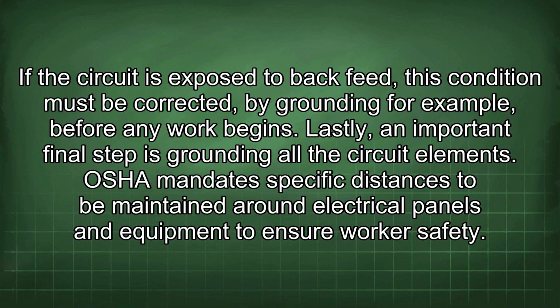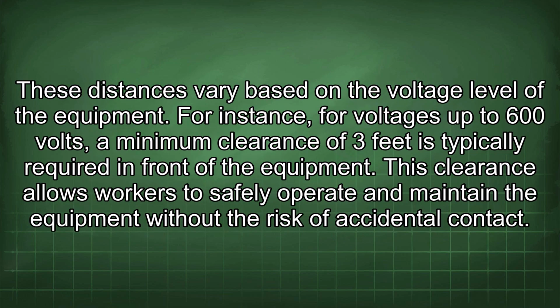OSHA mandates specific distances to be maintained around electrical panels and equipment to ensure worker safety. These distances vary based on the voltage level of the equipment. For instance, for voltages up to 600 volts, a minimum clearance of 3 feet is typically required in front of the equipment. This clearance allows workers to safely operate and maintain the equipment without the risk of accidental contact.